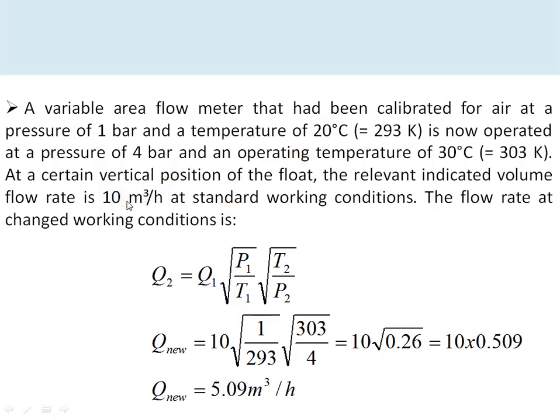At a certain float position the indicated volumetric flow rate is 10 m³/h at the standard working condition of 1 bar and 20°C. We need to calculate the actual flow rate at 4 bar and 30°C. Using the equation Q_2 = Q_1 × √(P_1/T_1) × √(T_2/P_2), the correction factor comes out to 0.509, so the actual flow rate is 5.09 m³/h — even though the float reads 10 m³/h.